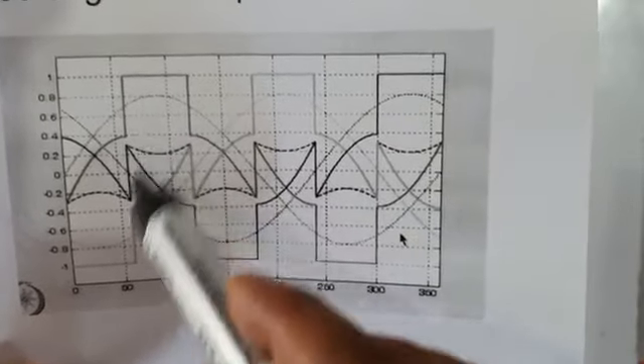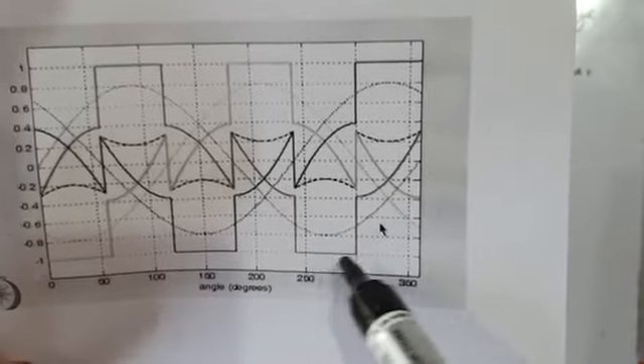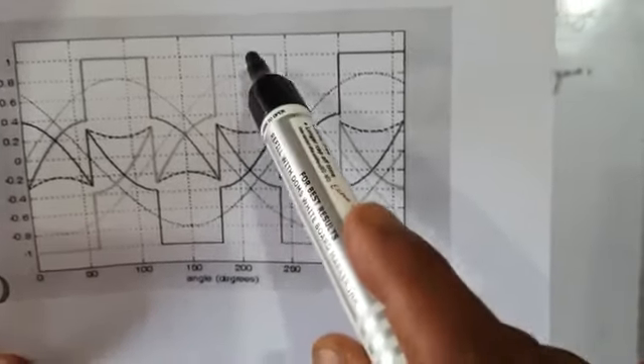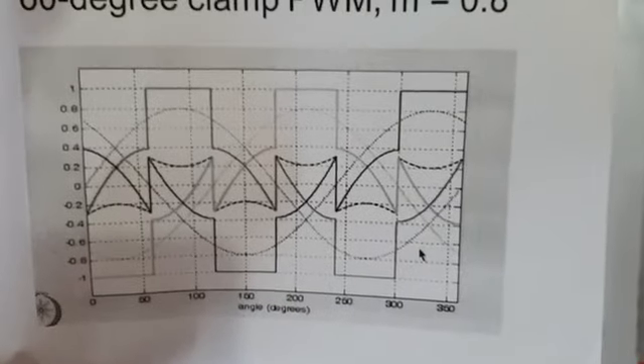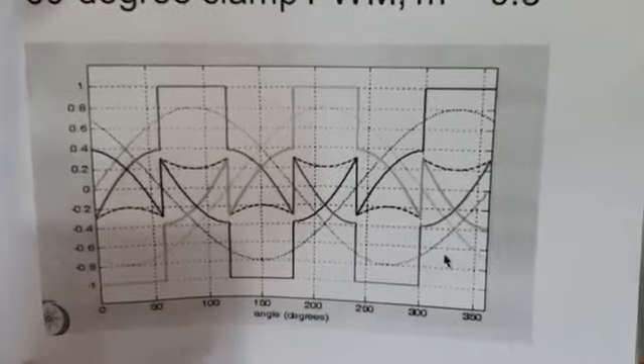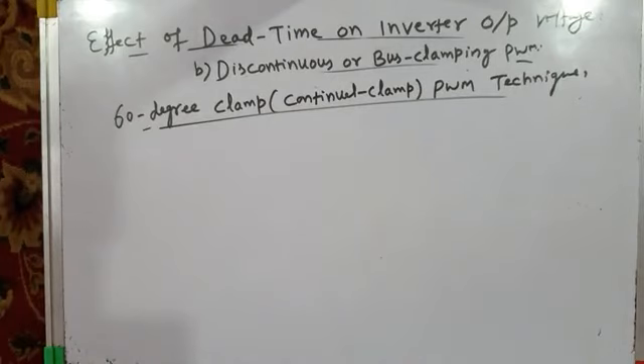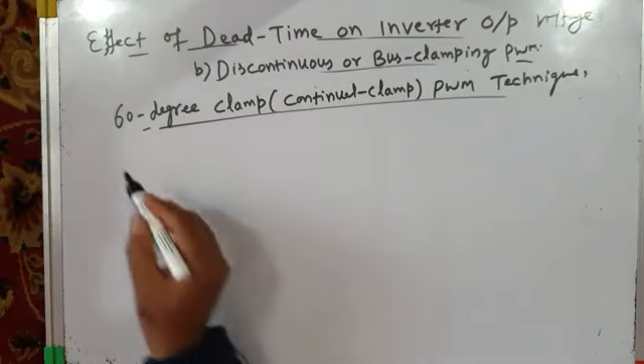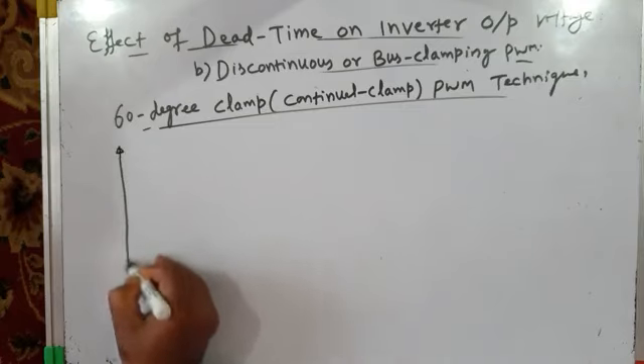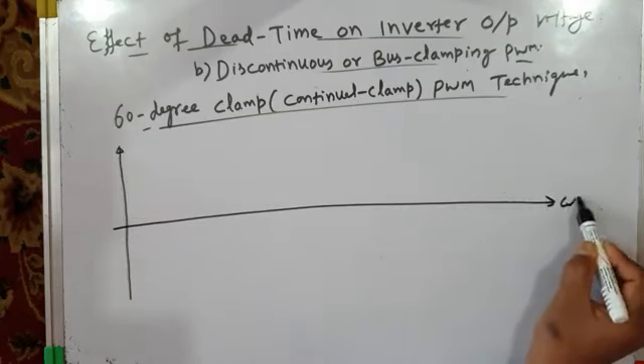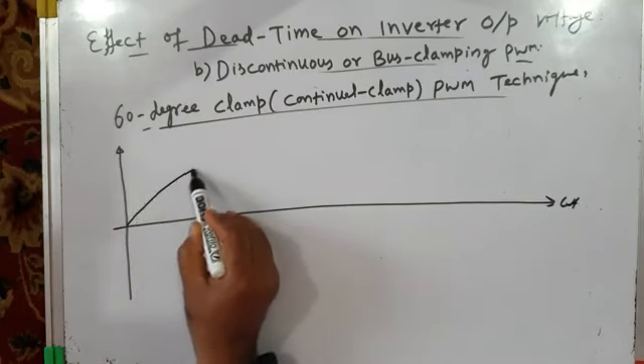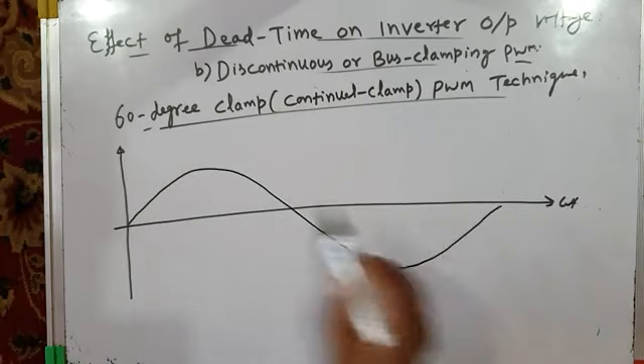All three phase legs are clamped to positive DC bus and negative DC bus in the middle of each respective half cycle. The basic concept of 60-degree clamp PWM has already been discussed in detail. To study the effect of dead time on this technique, we will draw just one phase waveform for clarity, considering only phase R.